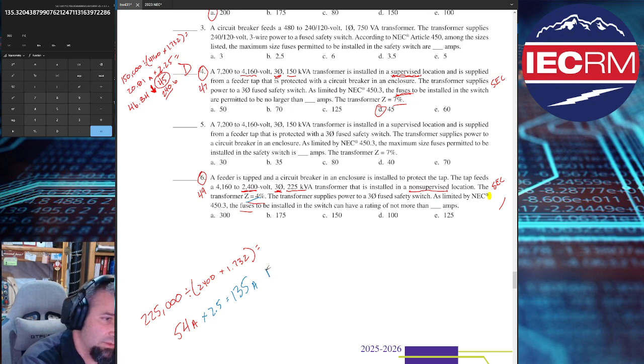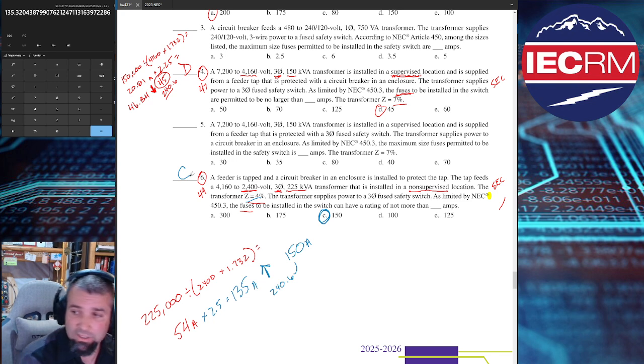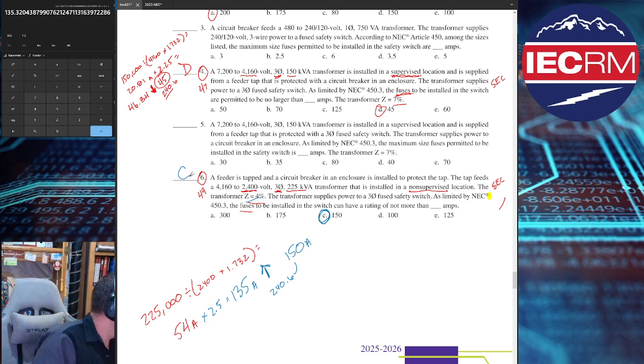So you're going to take a trip over to Article 240.6, find the next standard size, which is going to be 150 amperes. There you go, folks. We did it, we did it.